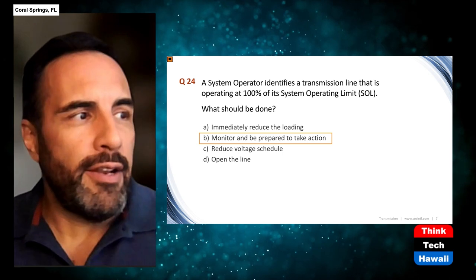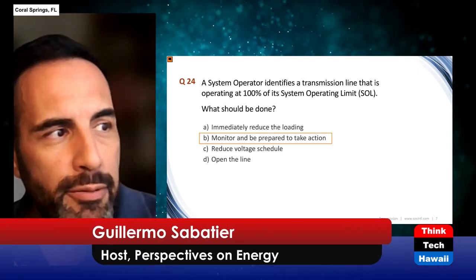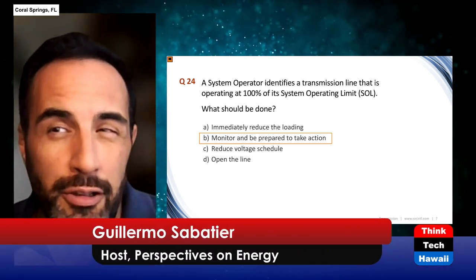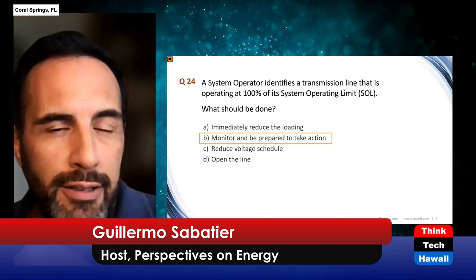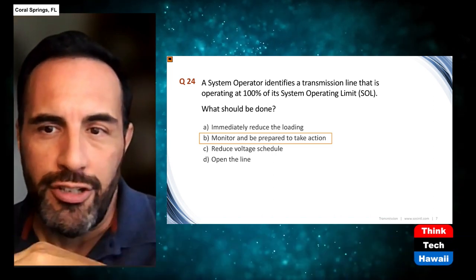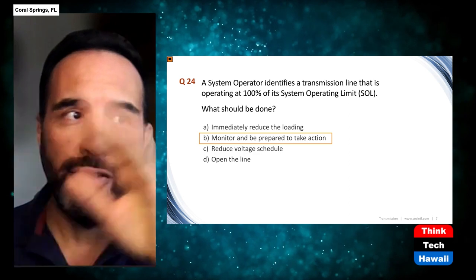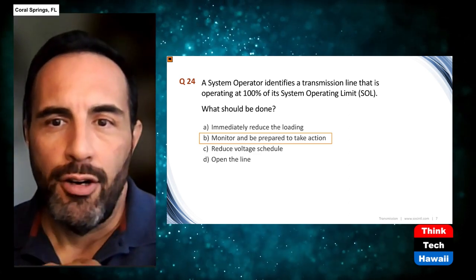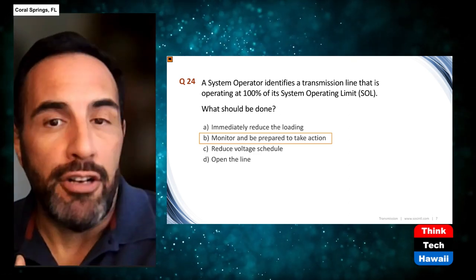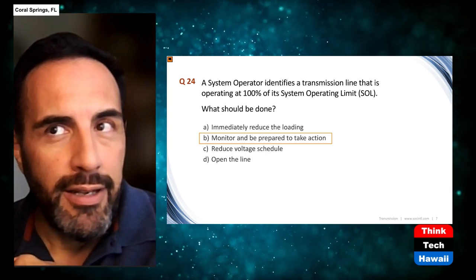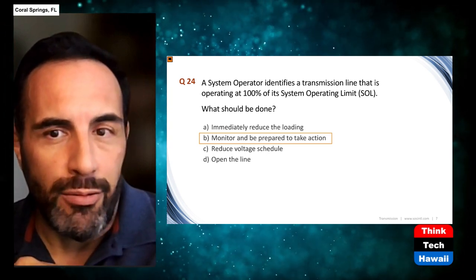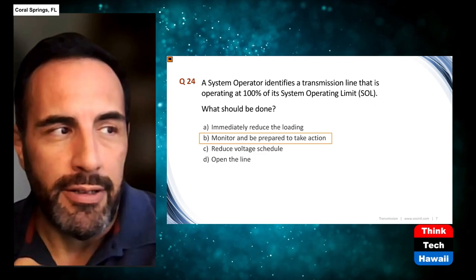So here you make an assumption. Do you want to immediately reduce loading? Well, how would you do that? Would you shed load? So you haven't really damaged the line. You haven't overloaded the line. You're just at the line's limit. Now, if you have something else happen, you may very easily overload this line or cause problems. But right now, nothing. Unless something changes in the wrong direction, nothing is really happening in this case.